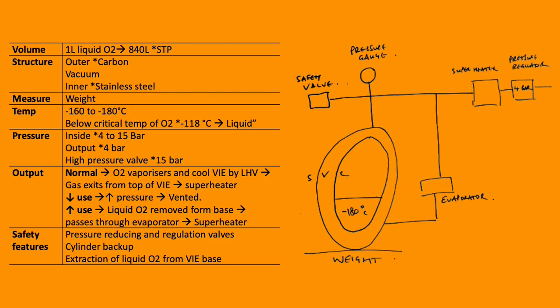It stores oxygen under the pressure of 4 to 15 bar at a low temperature of minus 160 to minus 180 degrees C. There's a pressure release valve set at 15 bar so excess gas is vented. You can measure the content of the VIE by weighing the VIE.